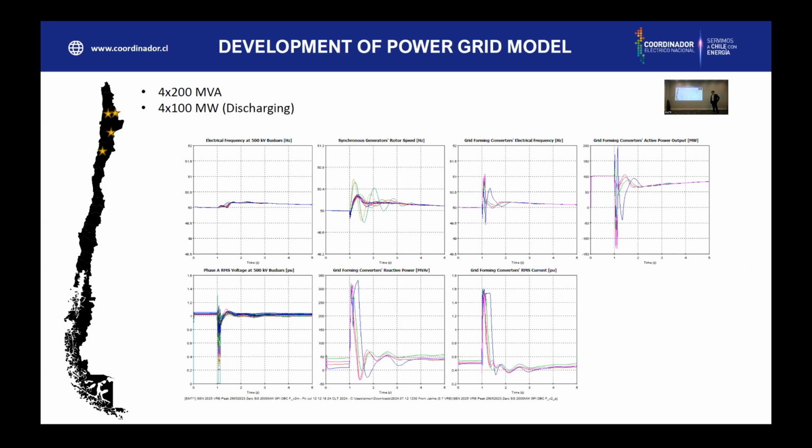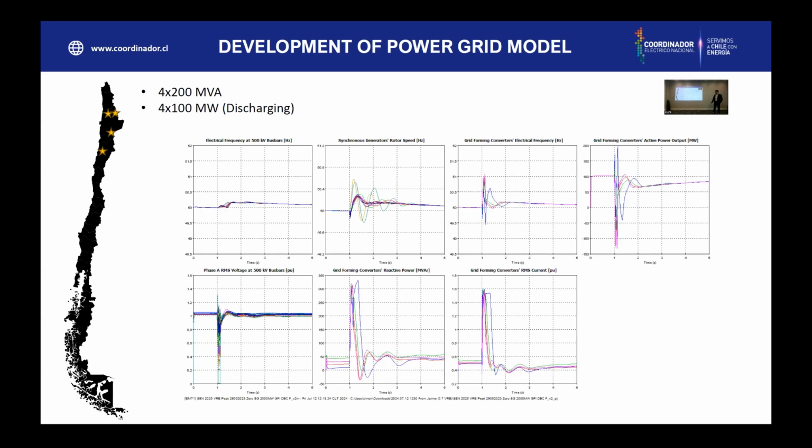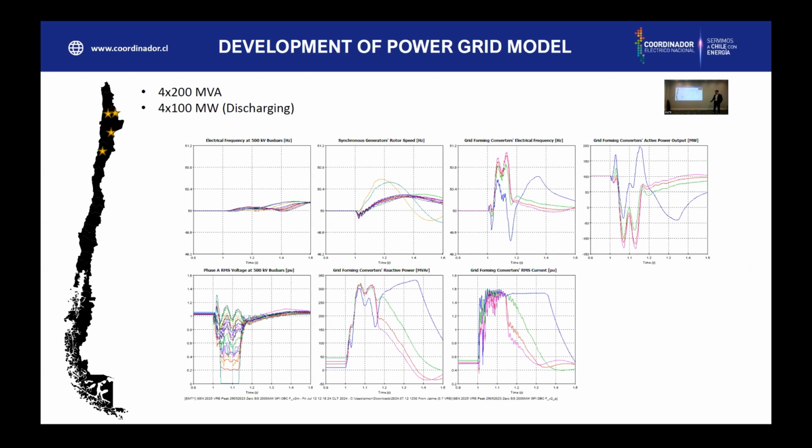So it's going dramatically fast. But with 70%, it's good. Besides, a paper that John and Jaime published this year had similar results, and they're all publicly available. But right now, the next step is, aside from analyzing what happens in the transient with the new grid forming model, to try it with 85% participation.